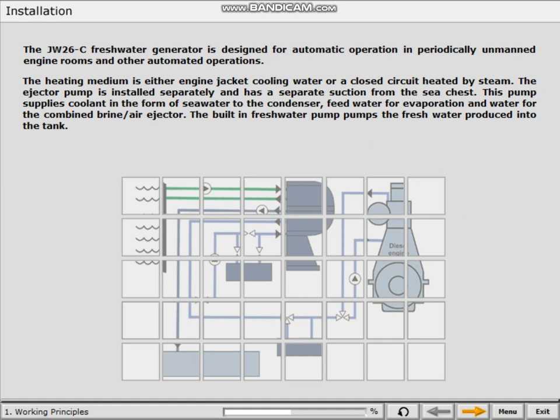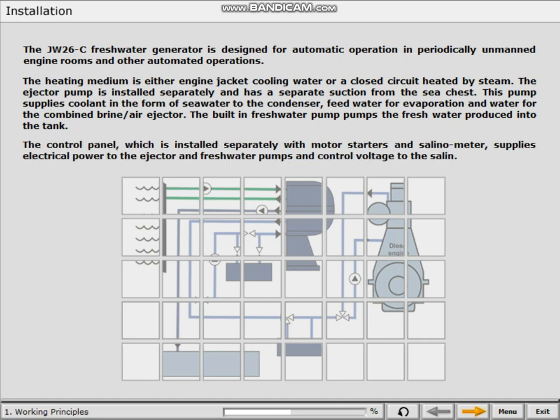The ejector pump is installed separately and has a separate suction from the sea chest. This pump supplies coolant in the form of seawater to the condenser, feed water for evaporation, and water for the combined brine-air ejector. The built-in freshwater pump pumps the fresh water produced into the tank. The control panel, which is installed separately with motor starters and salinometer, supplies electrical power to the ejector and freshwater pumps, and control voltage to the salinometer.